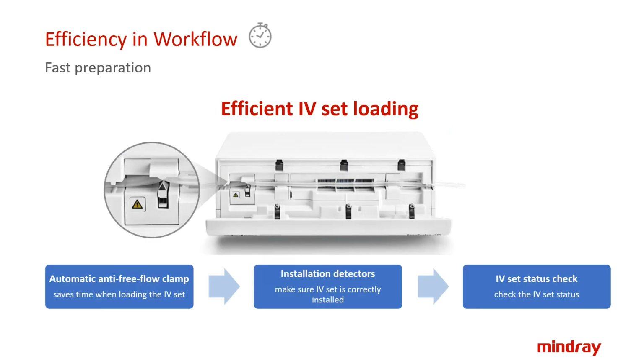Then we have the IV set loading efficiency. When we install the IV set, we can just open the door and place the IV set on the clamps of the pump. Then the clamp will automatically clip the tube, which saves time for loading the IV set. We have installation detectors to make sure the IV set is correctly installed, just like the picture shown here, to show you if the IV set is installed correctly or not. After the IV set is installed, the system does IV set status tracking to check if the IV set is ready. Then we can get the device ready to use.